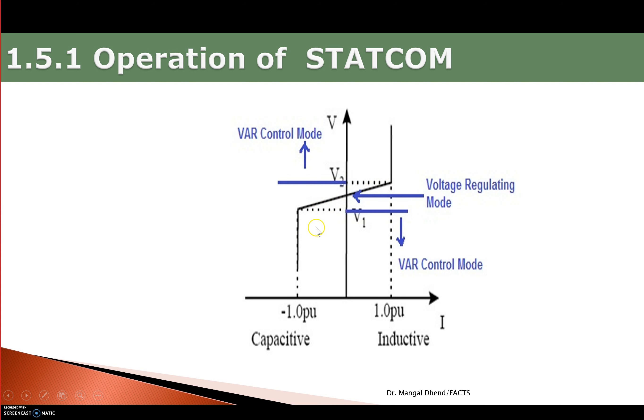The other region on the characteristics represents the VAR control mode. In VAR control mode, the inductive current remains constant and the capacitive current also remains constant at their respective limits. This flat region of constant current corresponds to the VAR control mode of STATCOM operation.